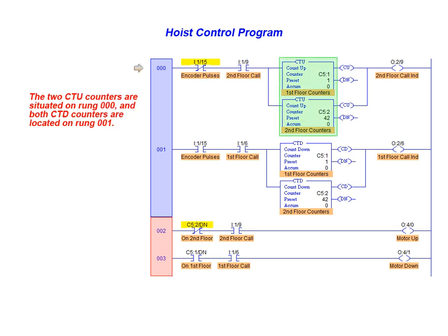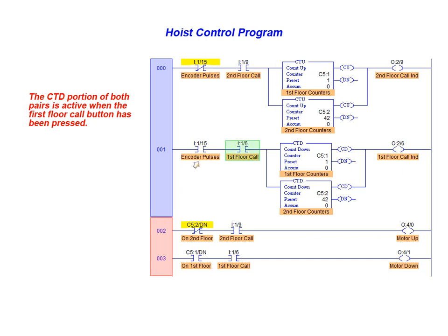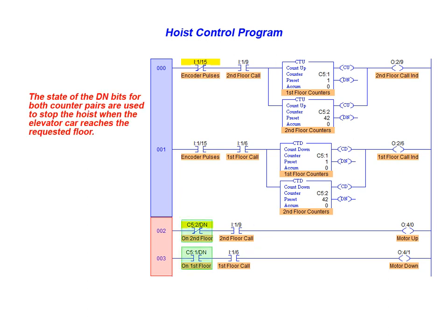The two up counters are situated on rung 0 and both down counters are located on rung 1. Pulses from the shaft encoder can only impact the up counters when a call to the second floor has occurred. Similarly, the CTD portion of both pairs is active only when the first floor call button has been pressed. The output control section also uses these two call button inputs to control the hoist direction. The state of the done bits for both counter pairs are used to stop the hoist when the elevator car reaches the requested floor.